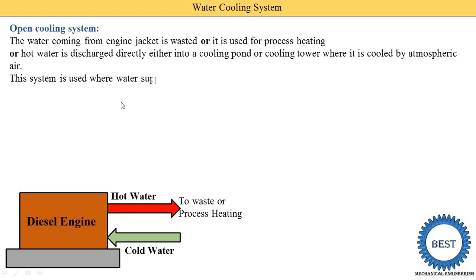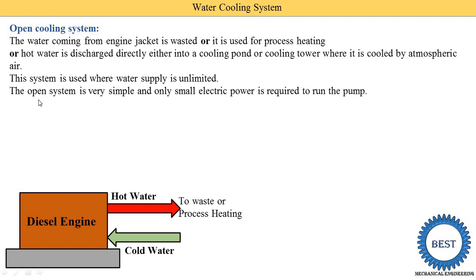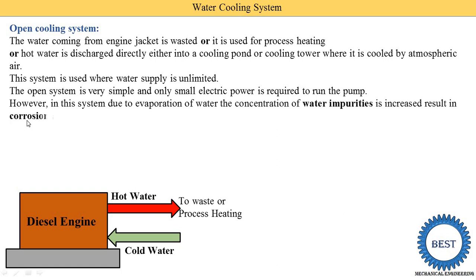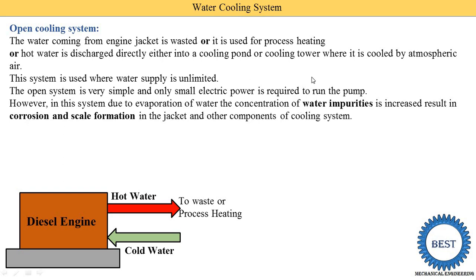This system is used where water supply is unlimited, meaning where the water source is continuously available. The open system is very simple and only a small electric power is required to run the pump. However, in this system due to evaporation of water the concentration of water impurities increases, and during this evaporation of water, impurities increase inside the engine. This results in corrosion and scale formation in the jacket — inside the engine the water jacket starts to corrode and scale forms because normal water is used.